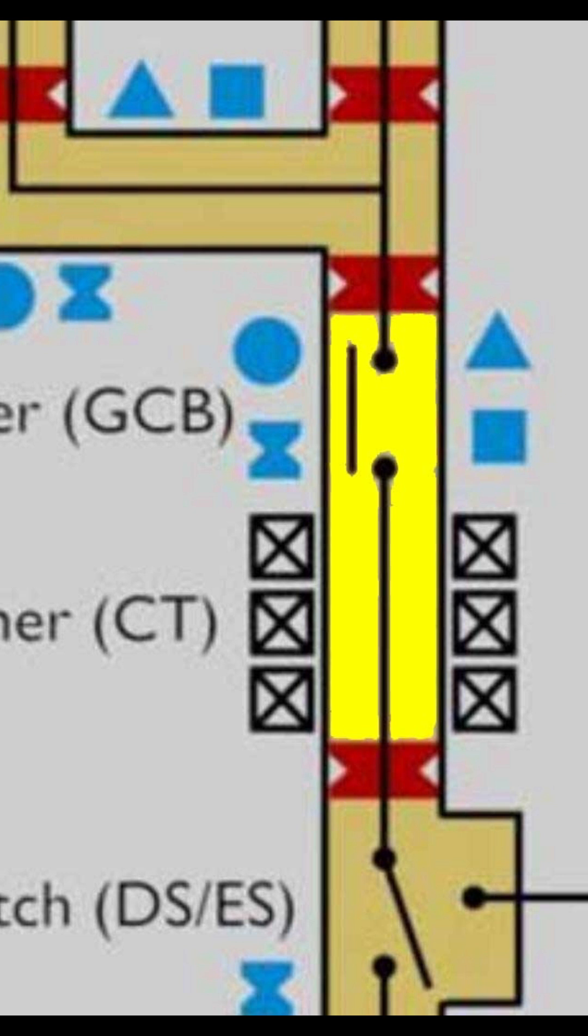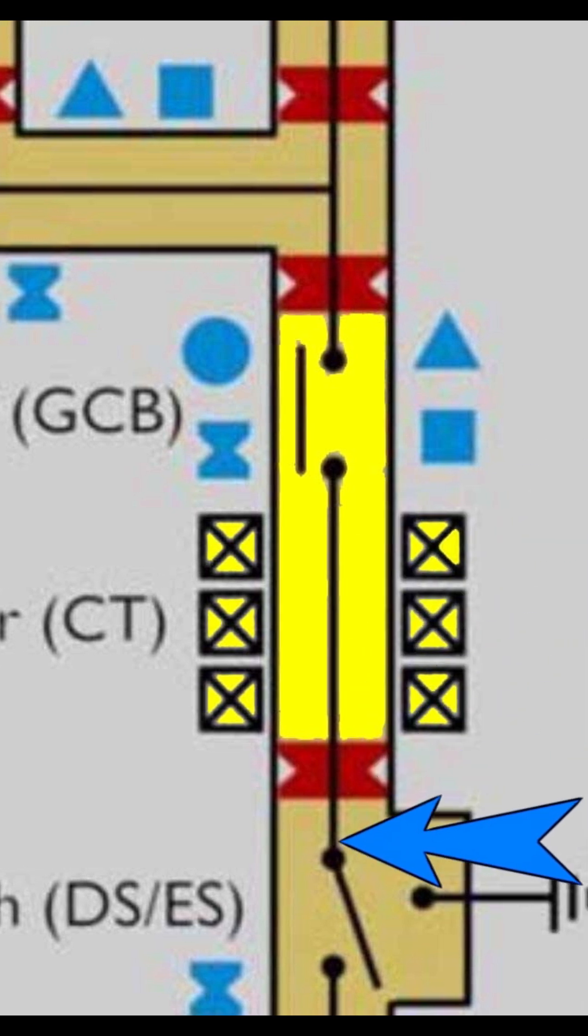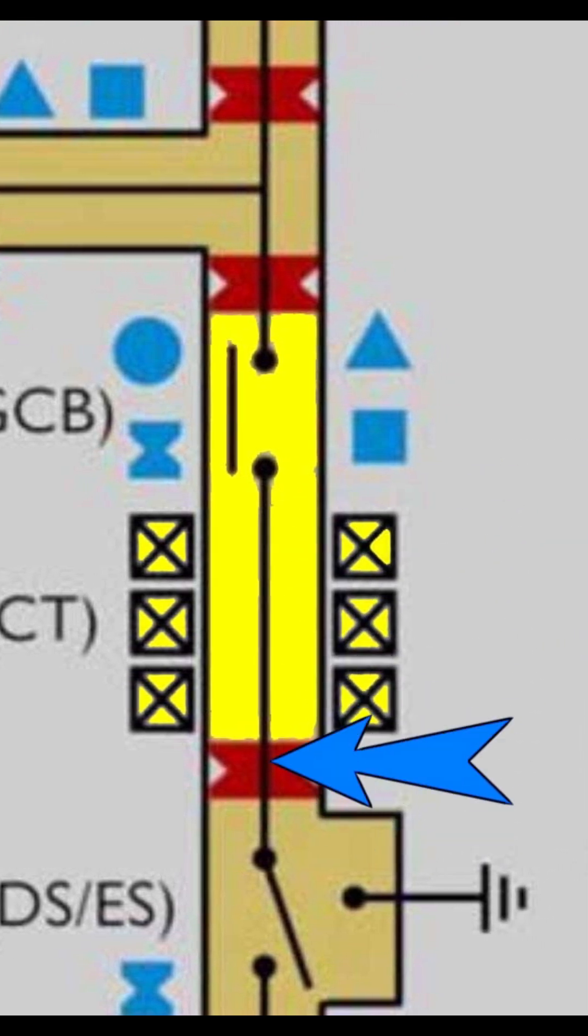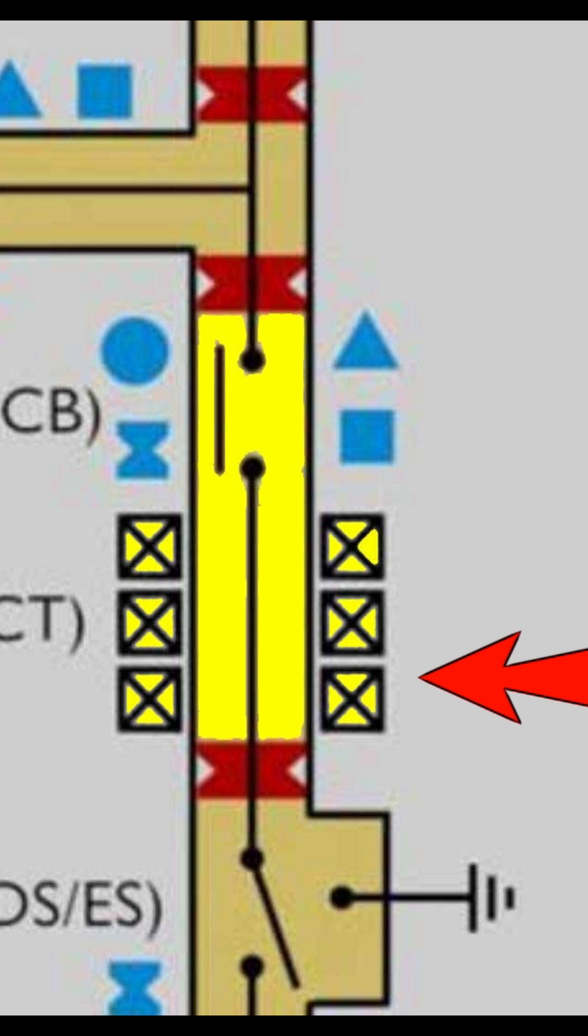In GIS, we generally do not use a gas-insulated CT. Instead, we just place the core of the CT around the GIS compartment. So the CT core surrounds the compartment. This conductor will behave like the primary of that CT, and these are the secondary windings on the cores.